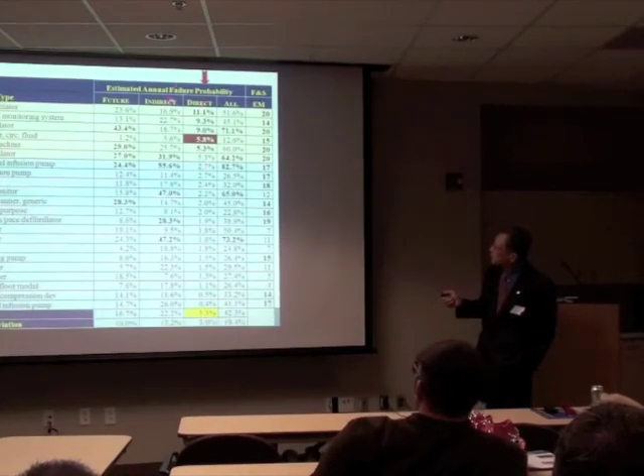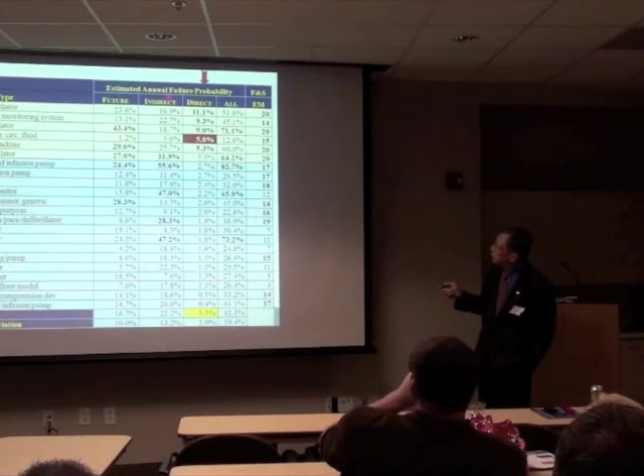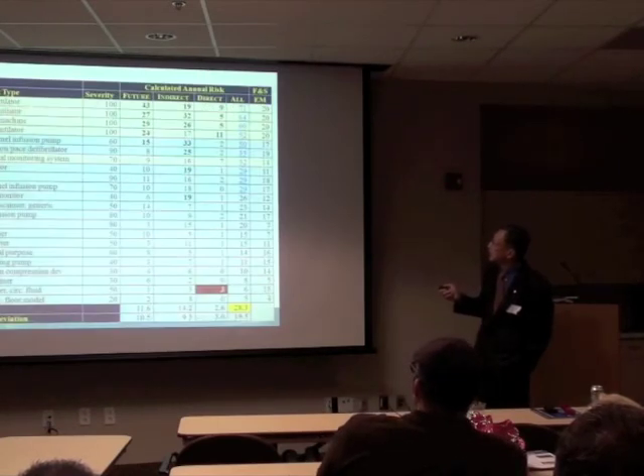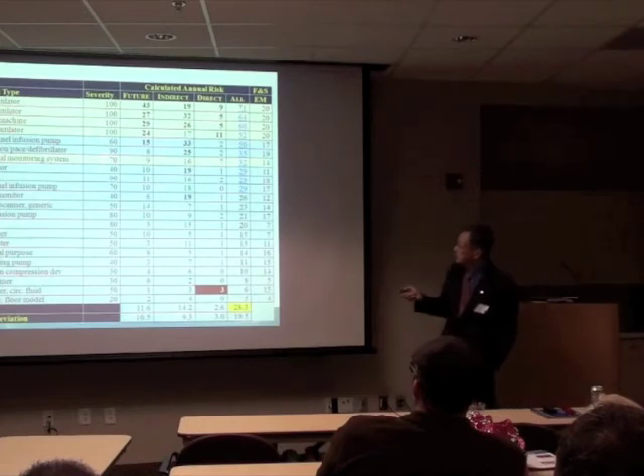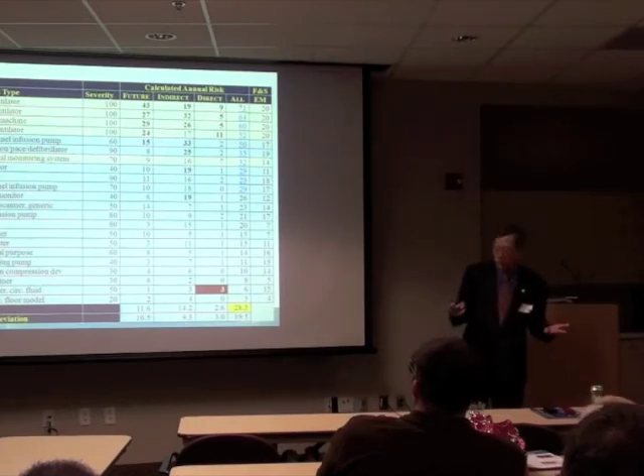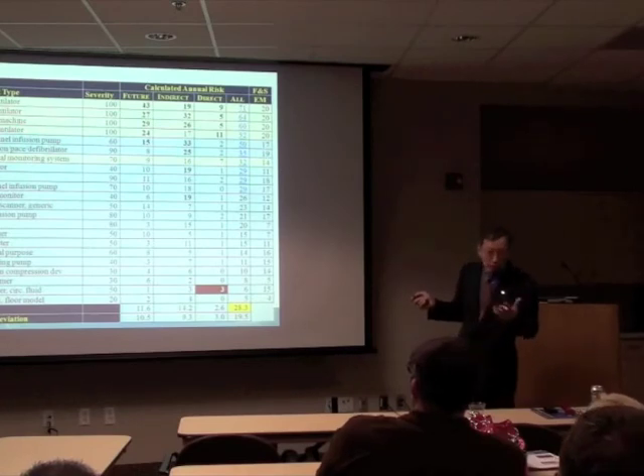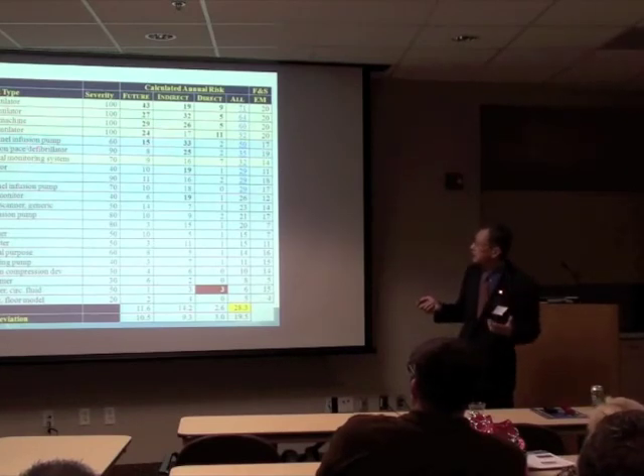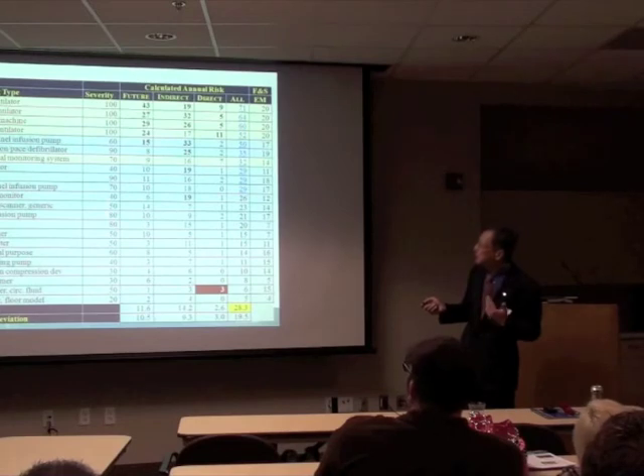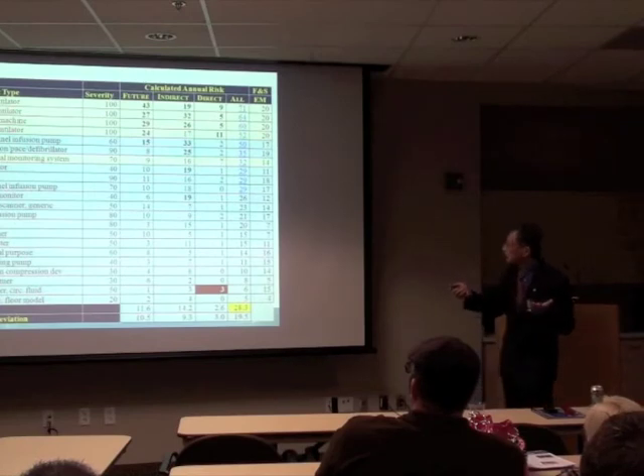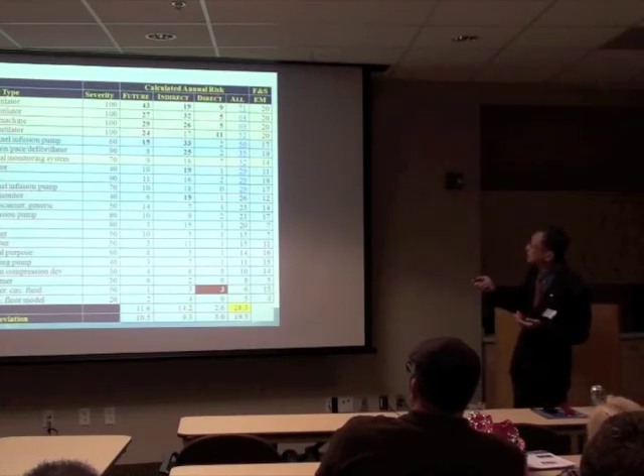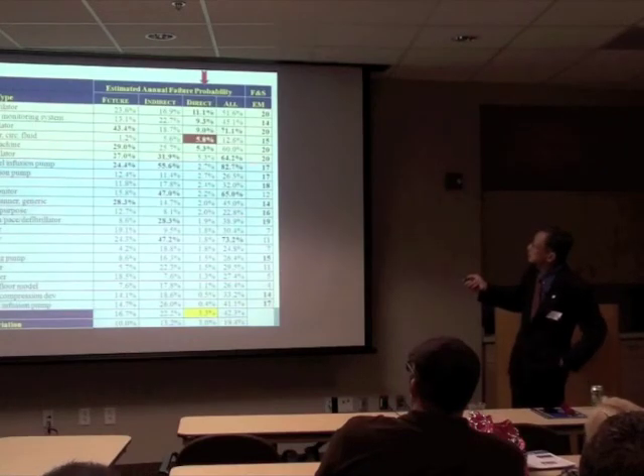If you think about the probability we calculated for all the different groups of equipment, we can use this probability and then assign a severity. Severity is assigned in the traditional way, based on whether this will affect the patient directly. Life support will obviously go up very quickly, but certain devices have very high numbers despite not necessarily being life support equipment. Whatever number you give, you can calculate the risk using the probability multiplied by severity.